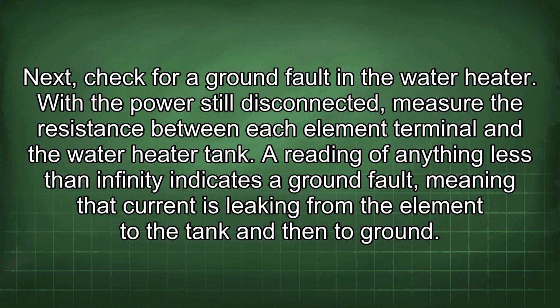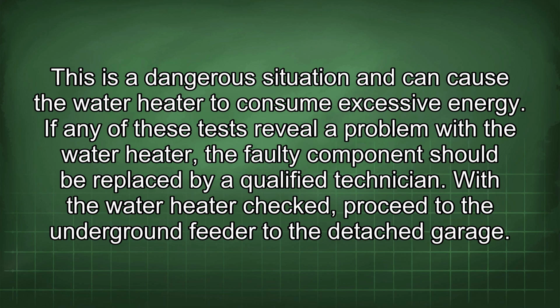A reading of anything less than infinity indicates a ground fault, meaning that current is leaking from the element to the tank and then to ground. This is a dangerous situation and can cause the water heater to consume excessive energy. If any of these tests reveal a problem with the water heater, the faulty component should be replaced by a qualified technician. With the water heater checked, proceed to the underground feeder to the detached garage.